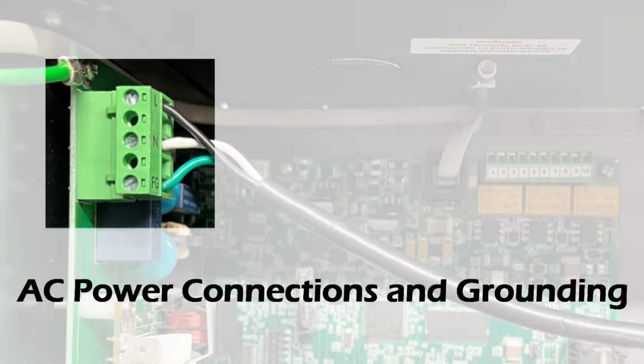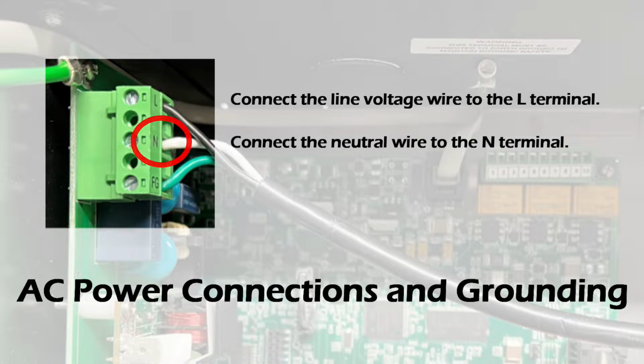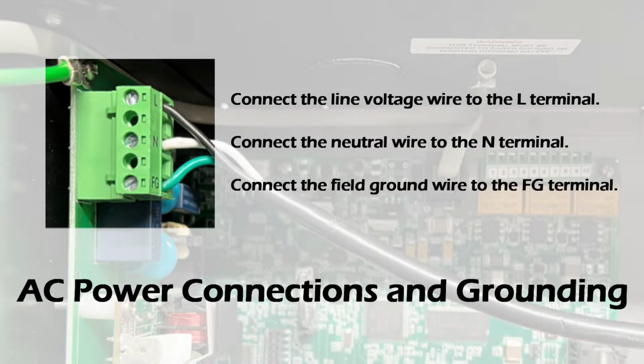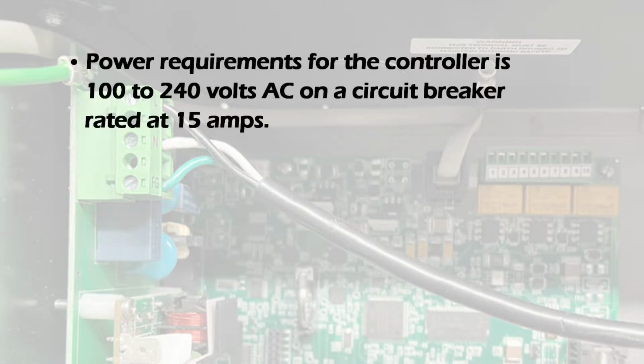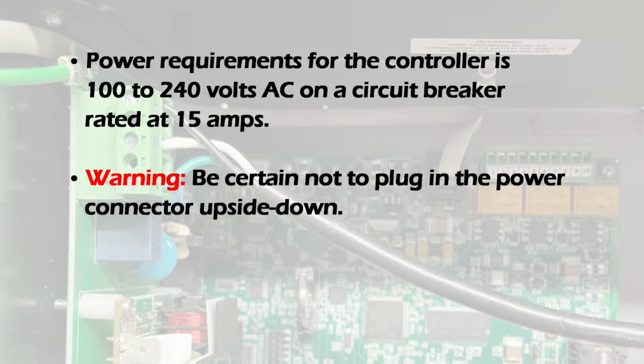Follow all electrical guidelines when connecting the AC power. Ensure the line, neutral, and field ground are correctly terminated on the power connector. Power requirements for the controller is 100 to 240 volts AC on a circuit breaker rated at 15 amps. Warning: be certain not to install the power connector upside down.